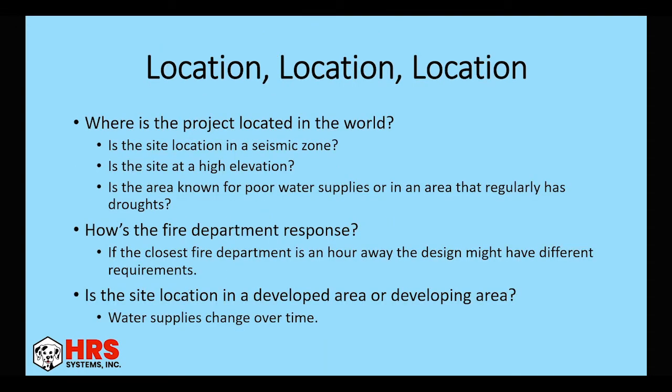The reason why you need to know the location is because of seismic zones. This can adjust your pipe sizing, because you can choose pipe sizing to get around seismic bracing. So this will have a large effect on your pipe sizes. Then is your site at a high elevation? If you do need a pump, this may change the size of pump you need. Also, you might be pumping water uphill, so the location of your pump or what size pump you need will be different depending on the elevation of your site. Then is the area known for poor water supplies? That right away could give you a dead giveaway of whether a pump is probably needed or not. How's the fire department response?